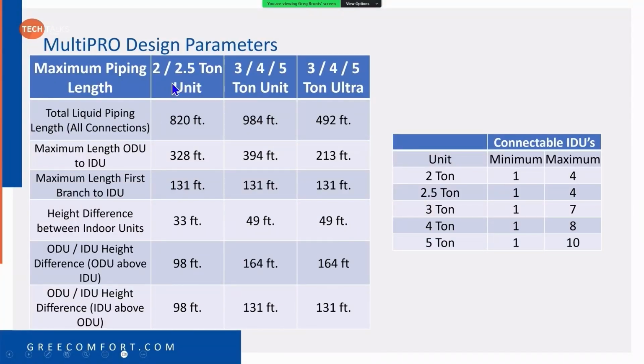Total liquid piping on a 2 and 2.5 ton is 820 feet. 3, 4, and 5 ton is 984 feet. 3, 4, and 5 ton ultra is 492 feet. Maximum outdoor unit to indoor unit, giving you all those dimensions as well. Maximum length from the first branch to the indoor unit, meaning from your Y branch or header, you can go up to 131 feet on all of them. Height difference between indoor units, that's from indoor unit to indoor unit, is 33 feet on 2 and 2.5 ton, 49 feet on the rest.